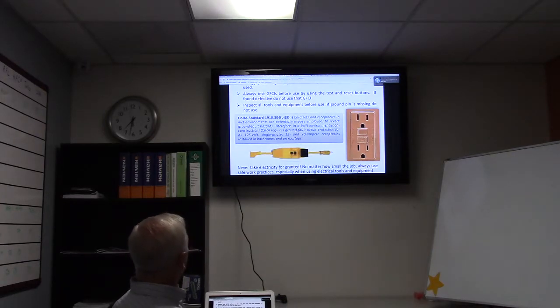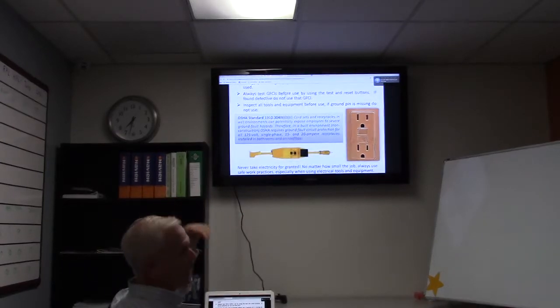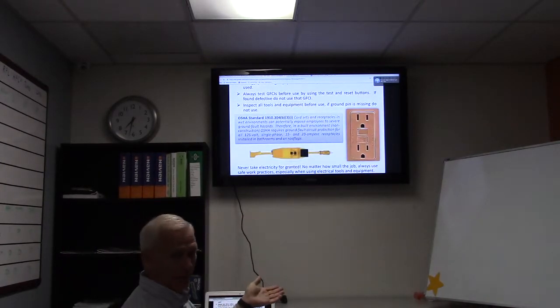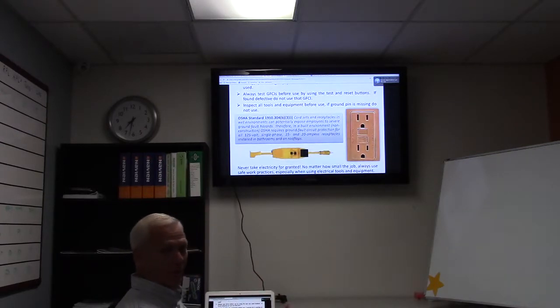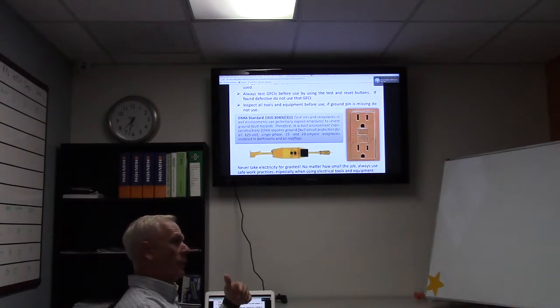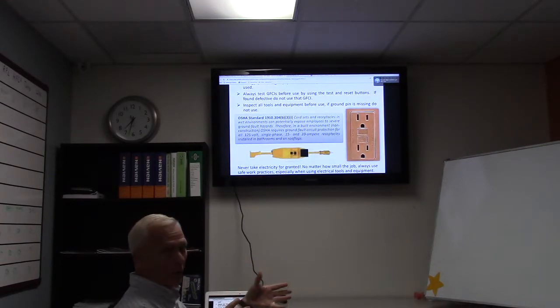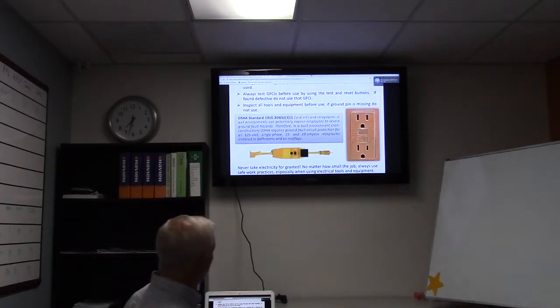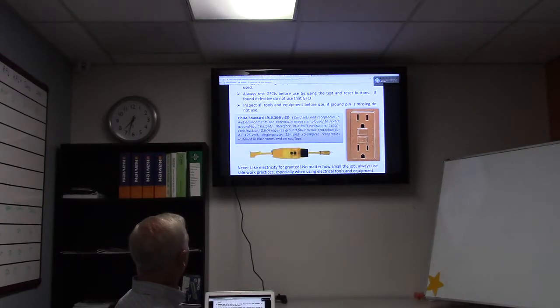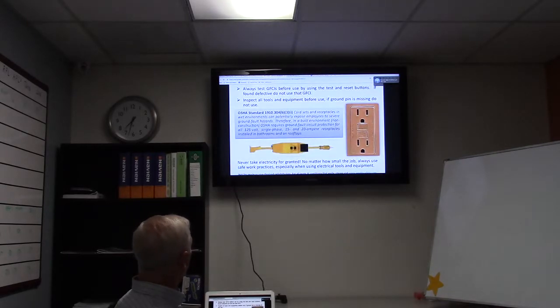So, cord sets and receptacles. A lot of times you'll also have a GFCI set in a cord. I know, like for a pressure washer, for example, right? There's water and electricity in the same application. Mine has a GFCI built into the cord, so it'll pop if there's some type of problem. Like if you're spraying with my pressure washer and I get water towards where the cord is plugged in, the GFCI will pop, right? So cord sets and receptacles in wet environments can potentially expose employees to severe ground fault hazards.